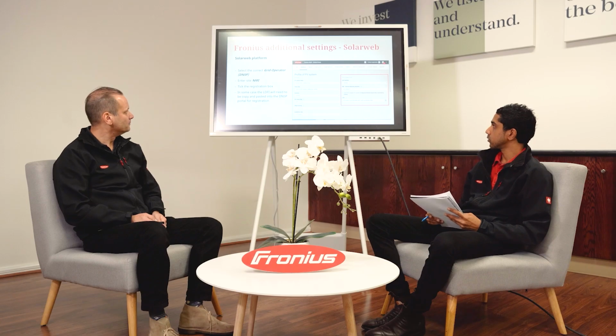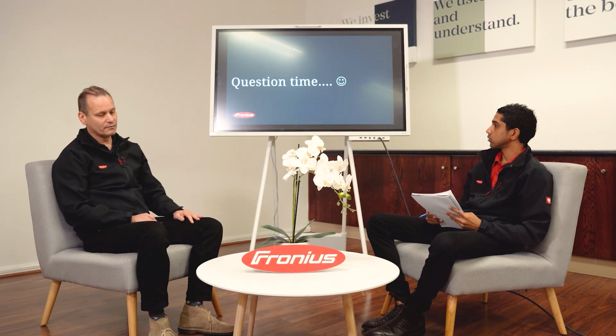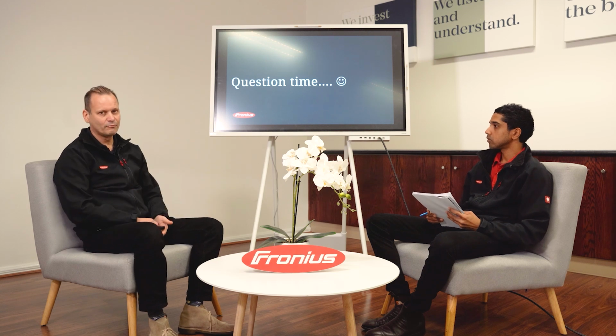Gemini, on the other hand, at the moment, doesn't have that in-band registration function, meaning that you'll need to manually register it. So that number will appear at the bottom, and it's not 100% clear yet how you'll do this, but in the Gemini portal, you'll need to copy and paste that number into the Gemini portal with the NMI, and that'll do the registration on their part. So that's pretty much it in Solar.web. That's all that needs to be done on that side of things. So that's kind of like the rough run through of what we know so far.